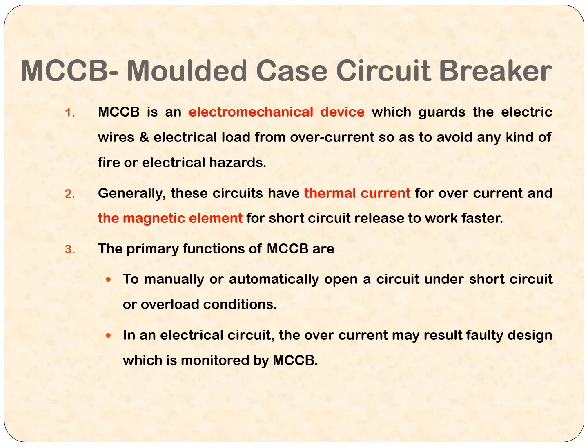Then what is it having extra? Generally, these circuits have thermal current for overcurrent protection and magnetic elements for short circuit release to work faster, which means a faster response is possible with an MCCB, and naturally it has the ability to adjust the limit of current to make it on and off.